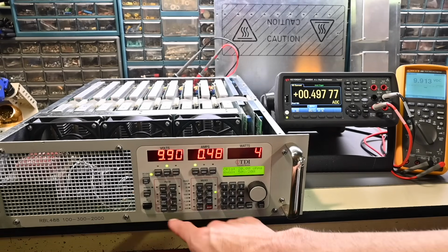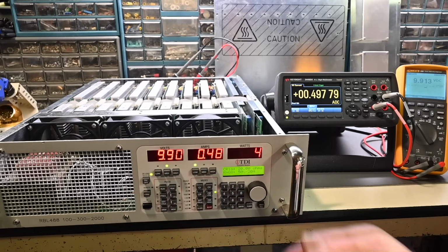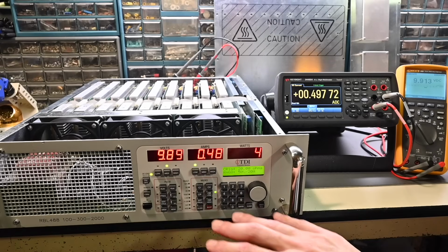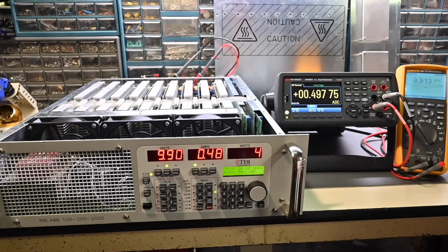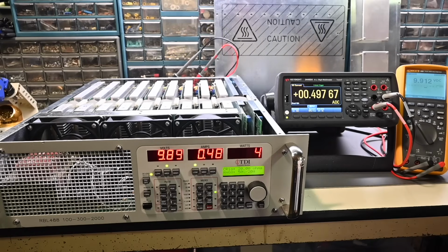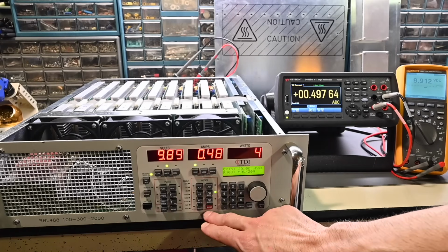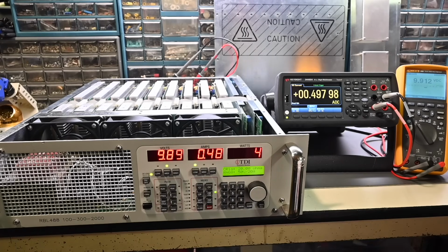And some of these other functions over here, the pulse modes or pulse generator for pulse load testing. It says short circuit right here. That's exactly what that means. It is a direct short. It essentially turns on all of those power FETs to their fullest. It completely saturates them, turns them on as hard as they can go, and it acts like a short. You have to be very, very careful with that mode, because obviously it's going to basically short out what you're testing. It's fine for testing power supplies that are intended to operate into a short, and you want to verify that. You never want to use the short circuit test on a battery or something, because it could cause extreme damage.